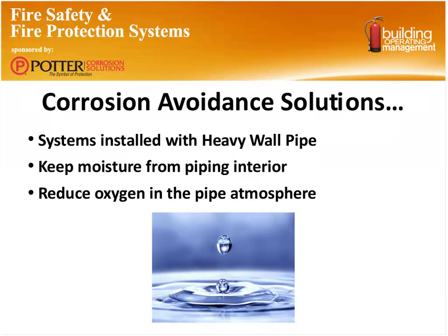So what can we do to avoid corrosion? Well, number one, make sure the systems are installed with heavy wall pipe if they're pre-action or wet or dry systems. But try to stay with a Schedule 40 pipe. Some of the thin wall pipes can have a problem, and in some cases, there's just not as much steel for that corrosion to work on. Keep moisture from the piping interior, and a very important piece here is to reduce oxygen in the pipe atmosphere.